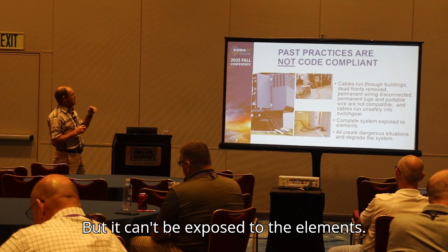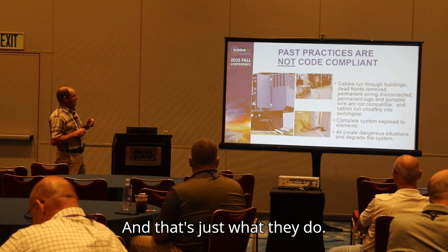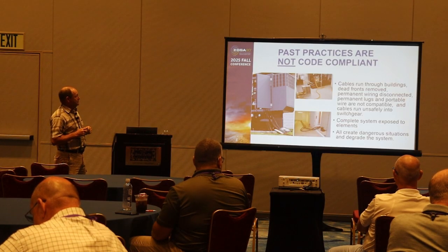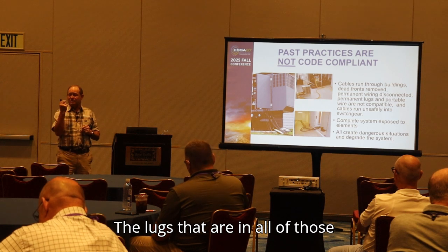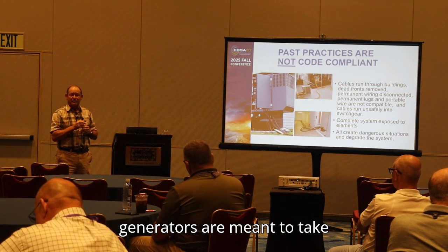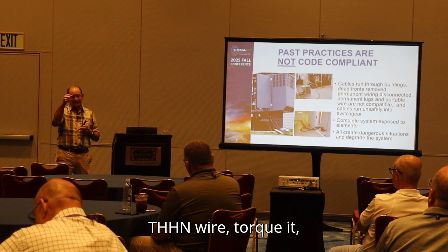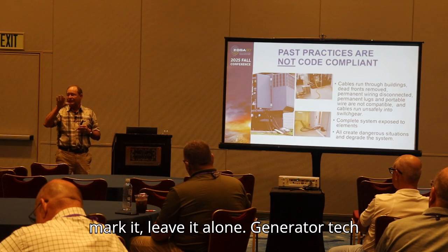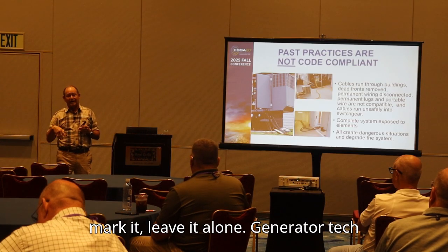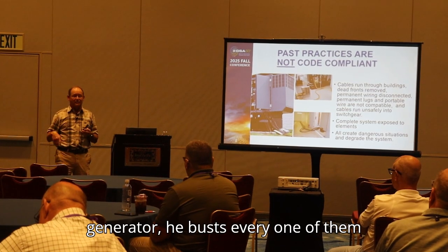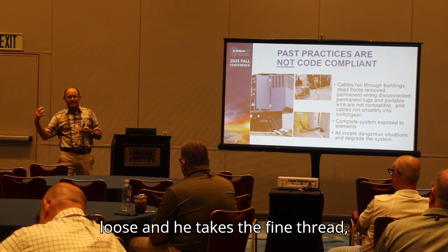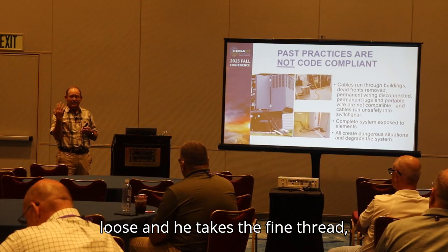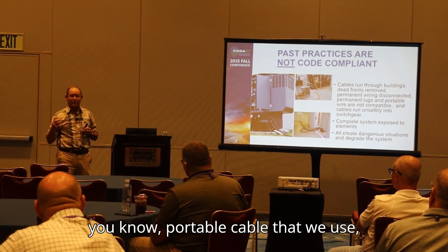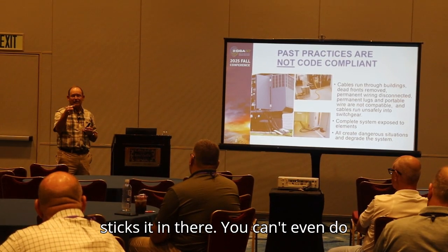It can't be exposed to the elements, and that's just what they do. The lugs in all of those generators are meant to take THHN wire, torque it, mark it, and leave it alone. The generator tech comes along, has to load bank the generator, busts every one of them loose, and sticks in the fine thread portable cable we use.